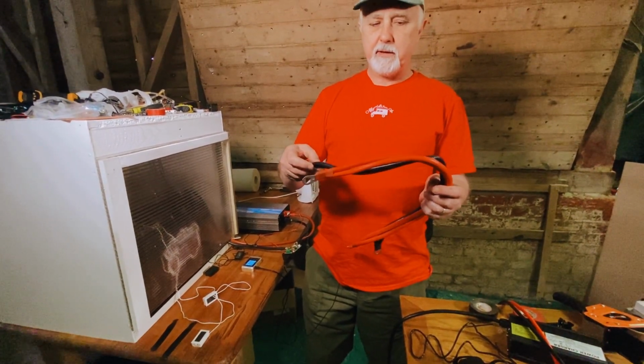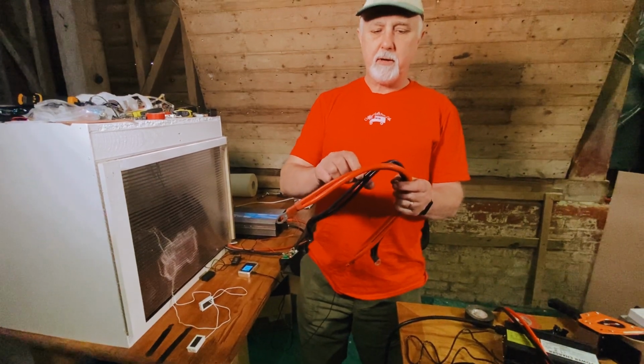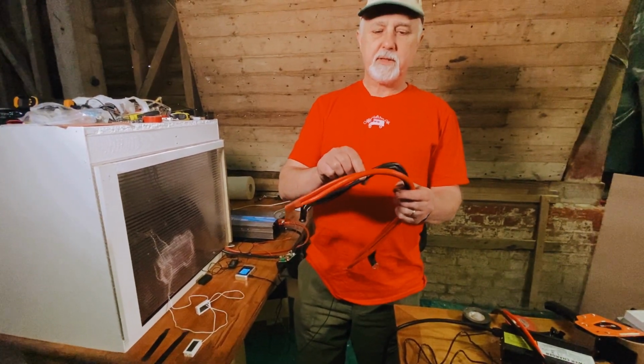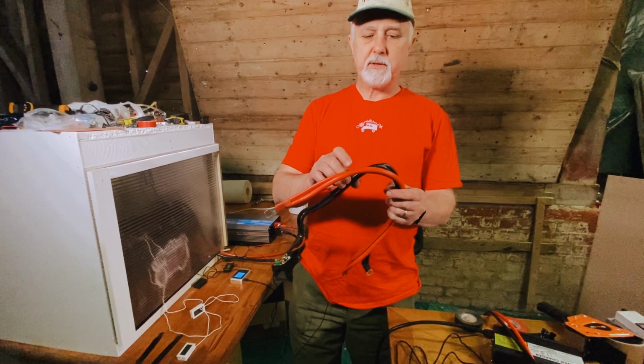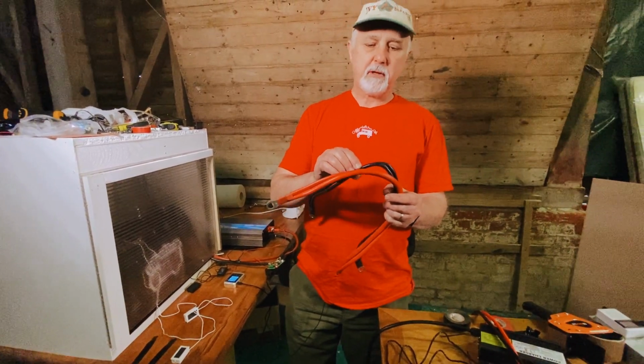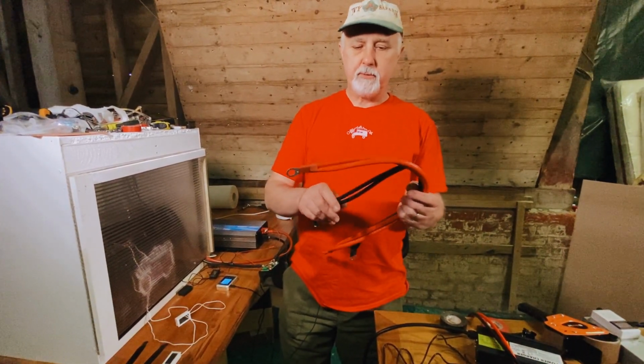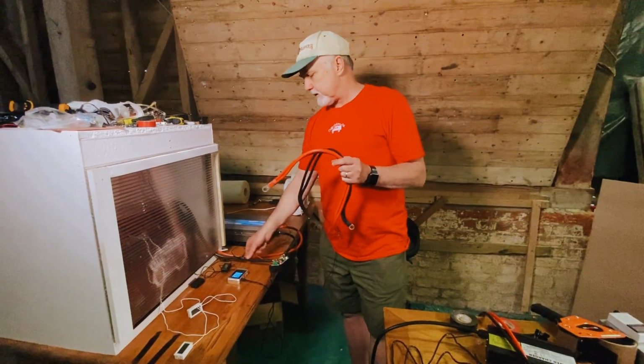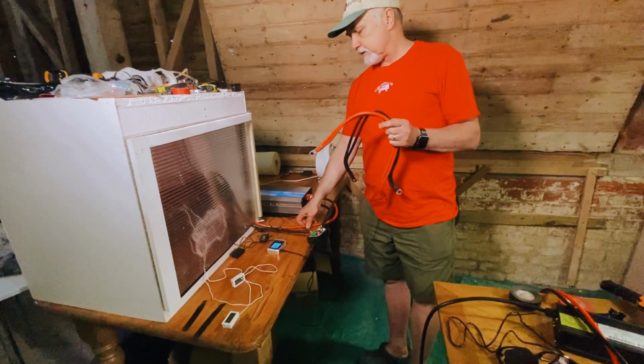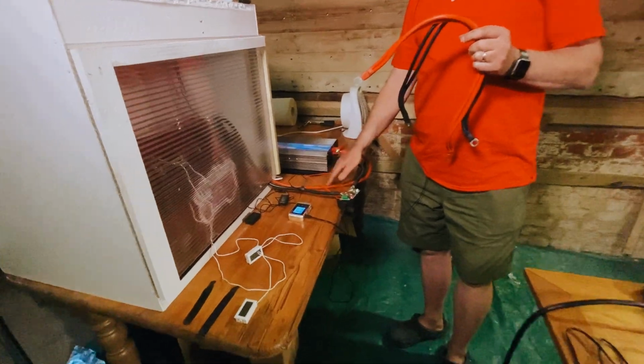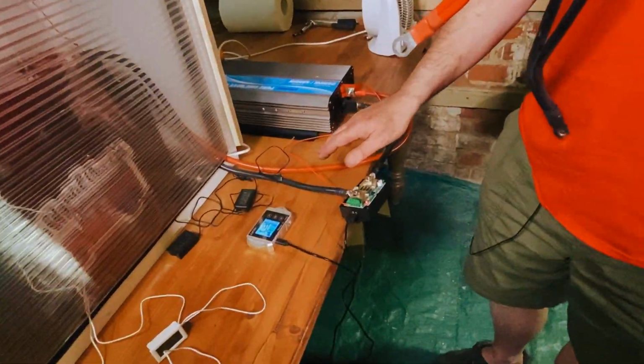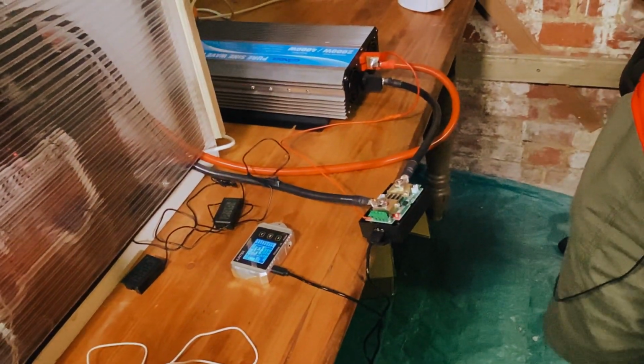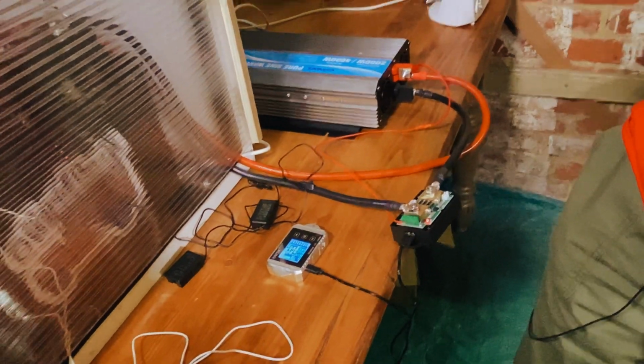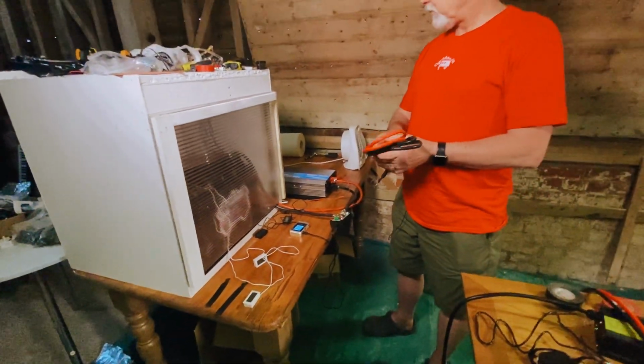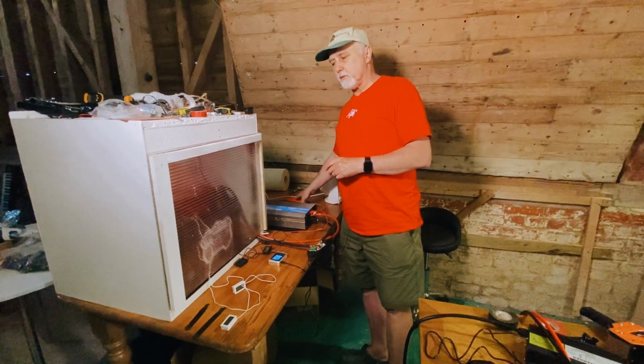Uncomfortably hot, and they are 2 16 millimeter cables, making up close on 35 millimeters in total. We made these 35 mil cables up, straight cables, that cope with the heat much better than these do. So let's see how the test progresses, and we will let you know the results when it's all done.